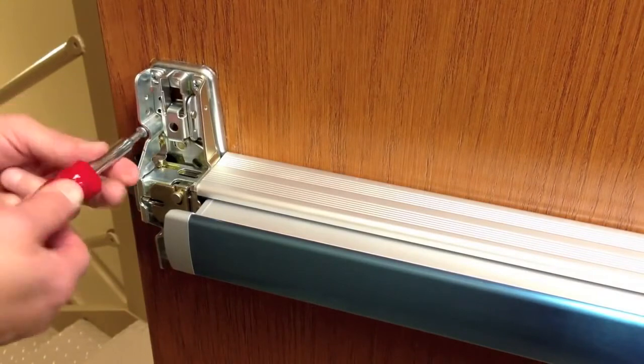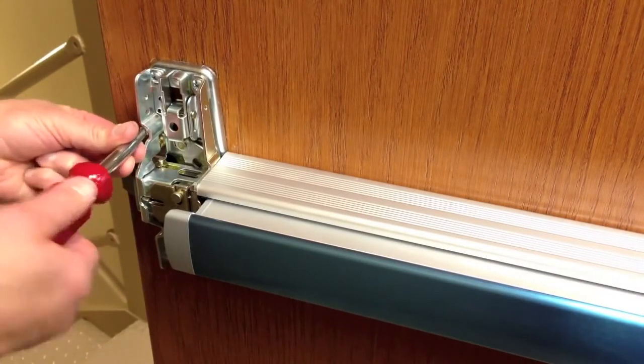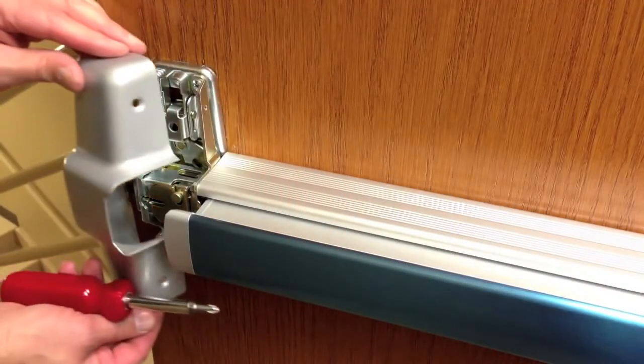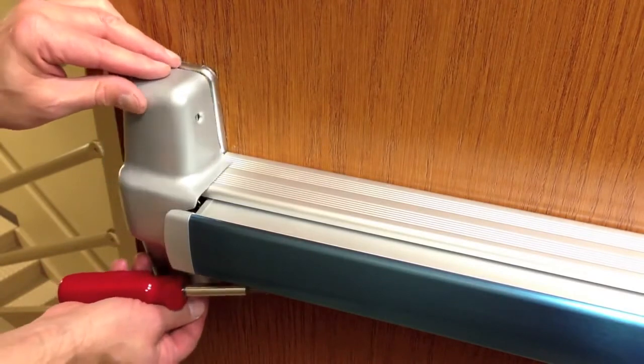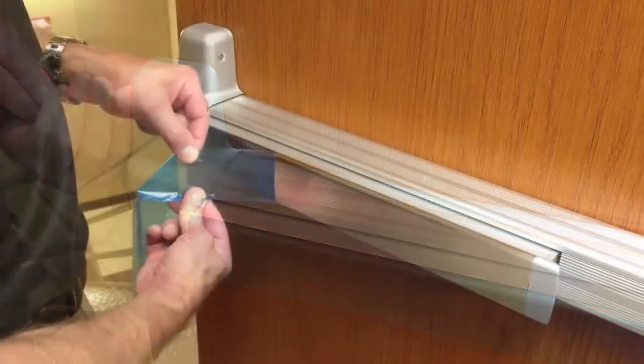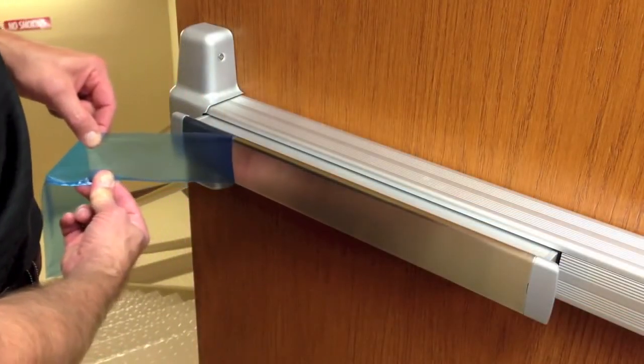Install the two support screws. For fire rated wood or composite doors, use sex bolts with the screws. Install the center case cover with the four provided screws. Remove the protective film from the push bar.